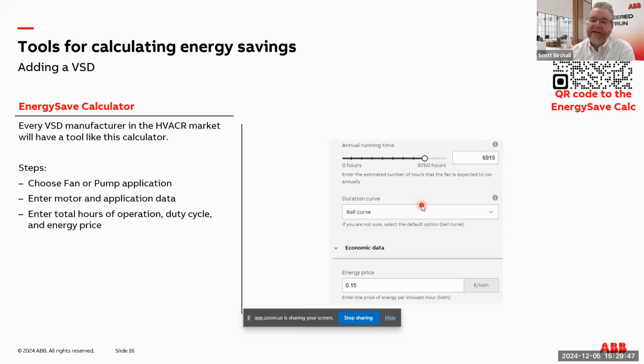the biggest and most important part of data that nobody ever has is what does that load curve look like? How often am I at 100% flow? How often am I at 90% flow? 80% flow? In the basic or advanced option, if you go advanced you can get down granular and enter all that data. Unfortunately, it's very hard to have that information unless you're trending sensor information. So a lot of folks use a generic bell curve that's common to HVAC - that's what I'm going to use as my default here. And then you put your energy price in down here.